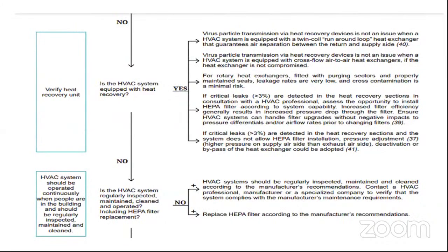Now, is the HVAC system equipped with heat recovery? This is the only thing which is different from the natural ventilation system. We need to verify the heat recovery unit. We need to make sure that the HVAC system is equipped with cross-flow air-to-air heat exchangers. If there are leaks, they need to be detected, and this is where the role of the HVAC professional comes into being. Is the HVAC system regularly inspected, maintained, cleaned, and operated?